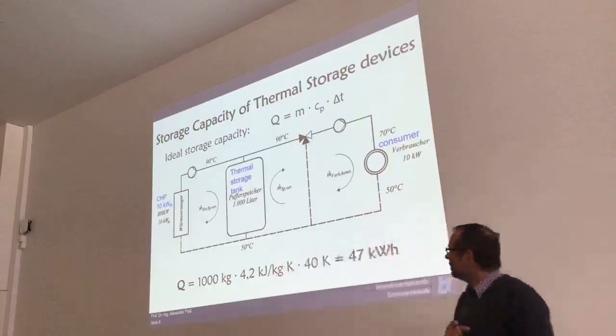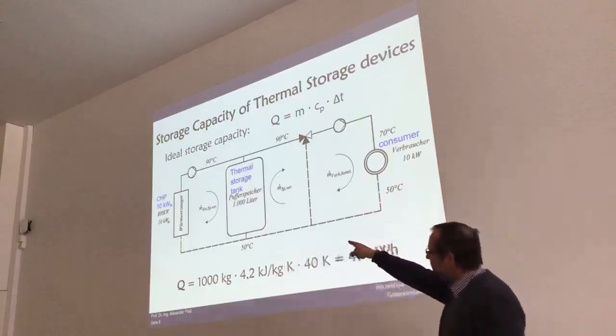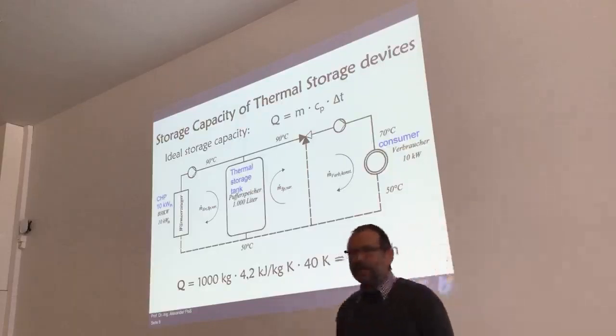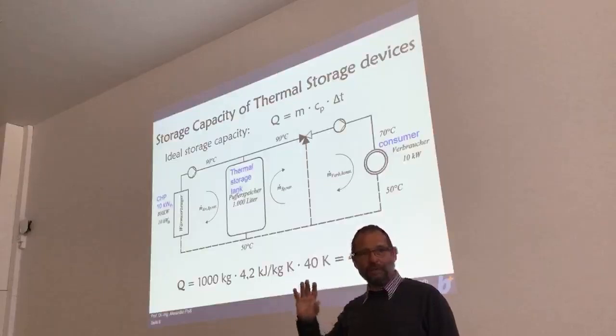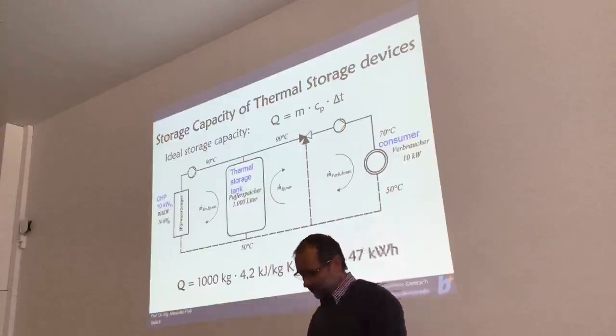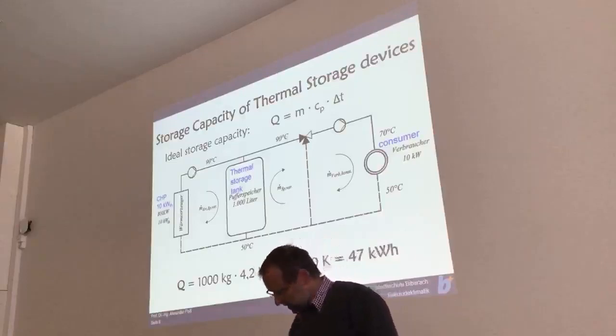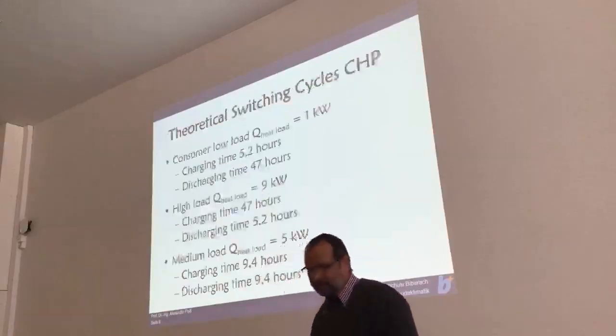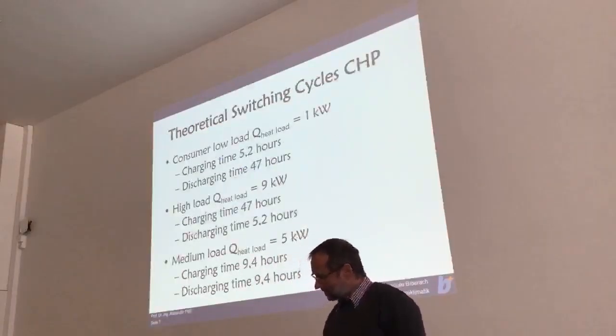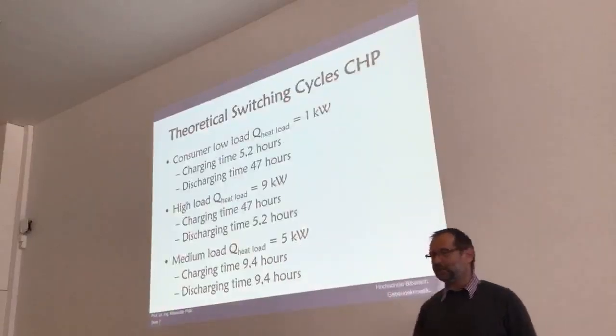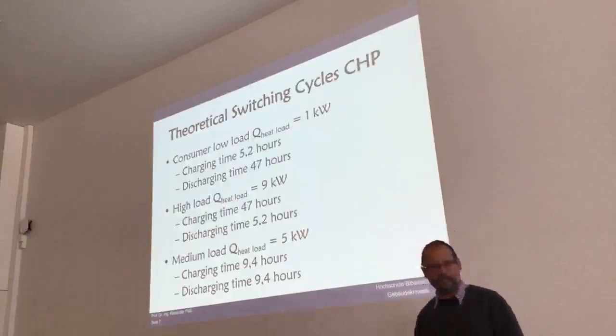It's important to mention that the CHP was only able to run under nominal load. So it was only able to switch on and off. It had no possibility of running under part load conditions. We now did some theoretical considerations about the switching cycles of the CHP.